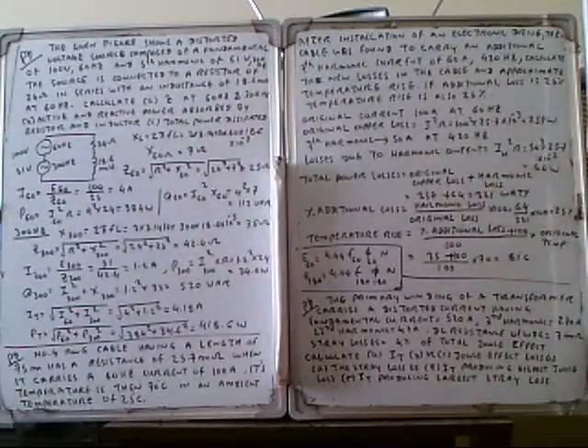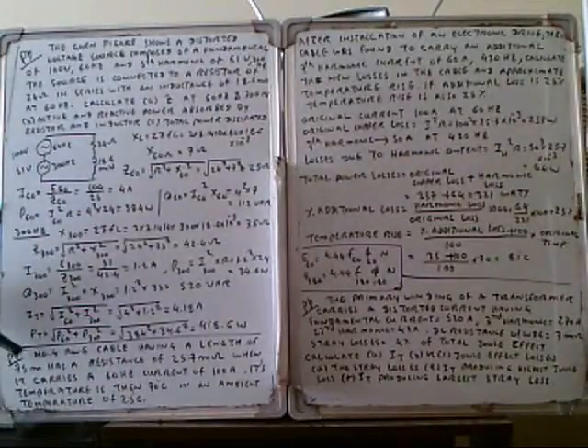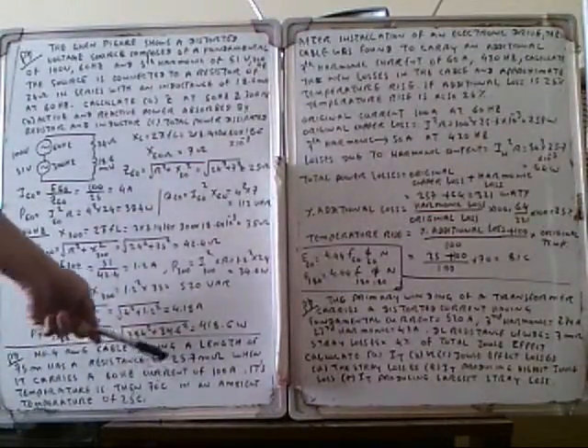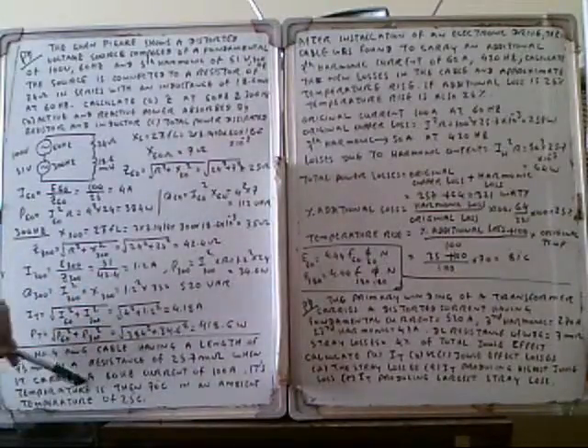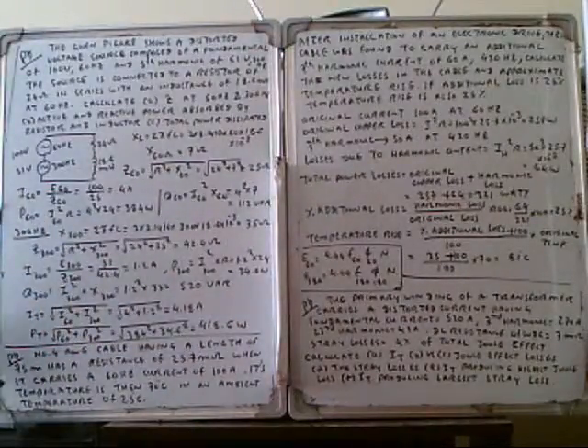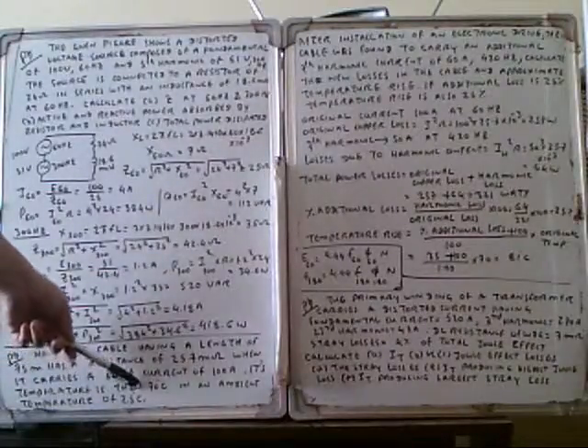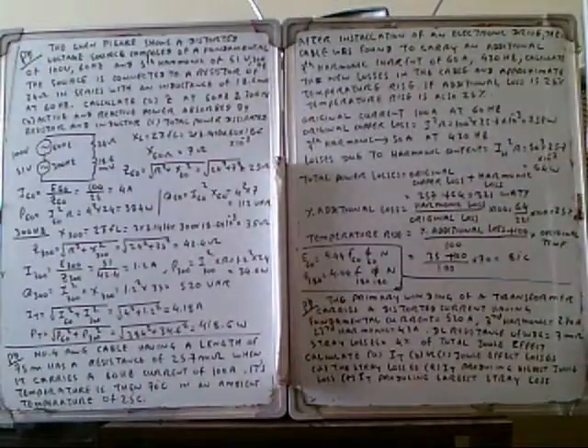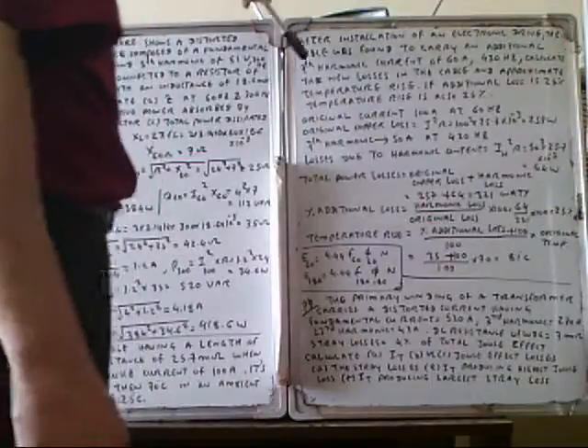Another problem: Number 4 AWG cable having a length of 35 meters has a resistance of 25.7 milliohms. When it carries a 60 Hz current of 100 amps, the temperature is then 70 degrees centigrade in an ambient temperature of 25 degrees. After installation of the electronic drive, the cable was found to carry an additional 7th harmonic current of 50 amps at 420 Hz. Calculate the new losses in the cable.